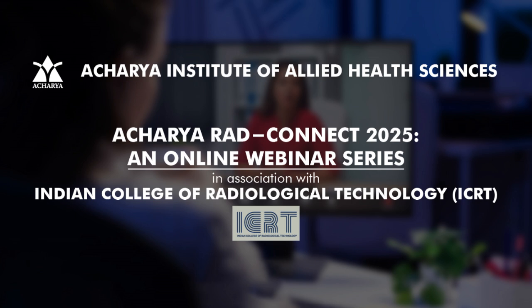And what is the difference between automatic exposure control and tube current modulation? What automatic exposure control does is it stops the exposure when enough photons have reached the detectors. Exposure needs to be terminated also. Exposure cannot go on continuously. AEC is not only used in CT scans, it is used in DRs, mammography, digital mammographies, everywhere.